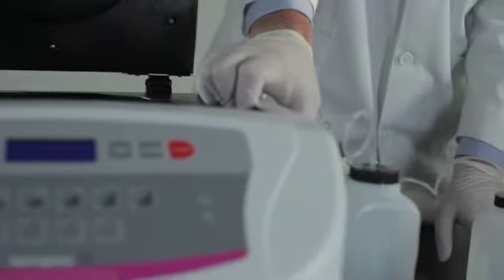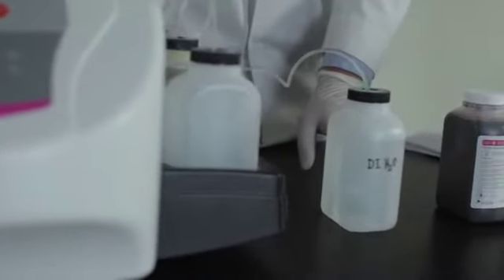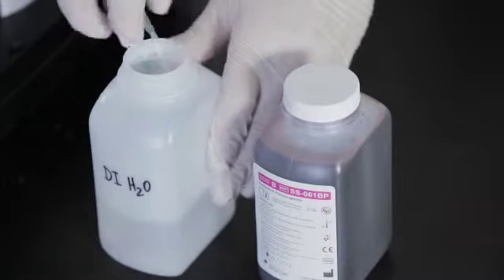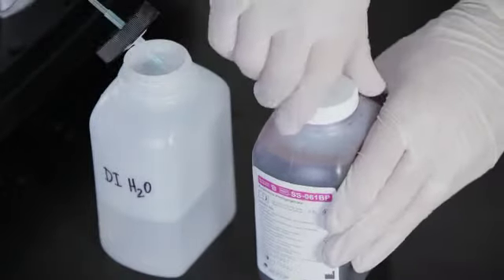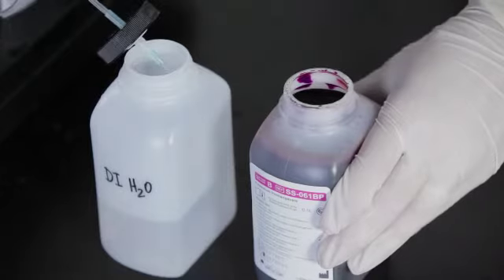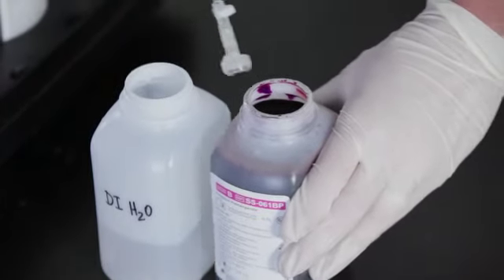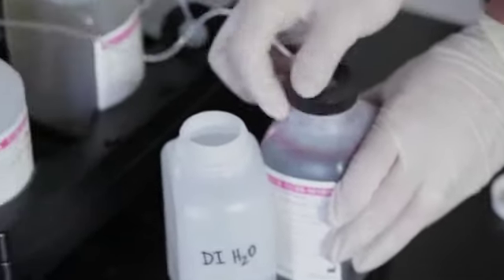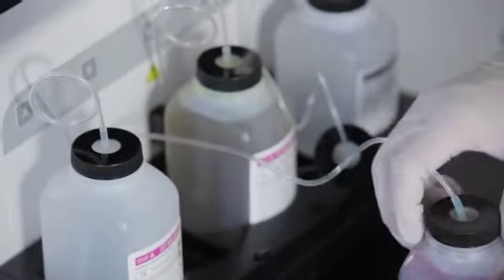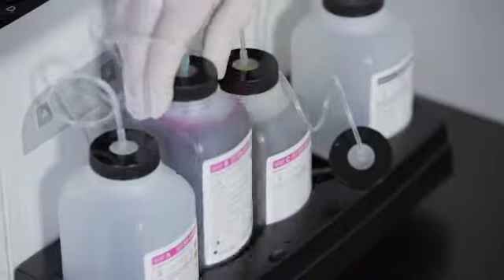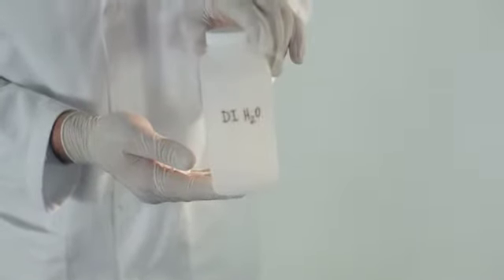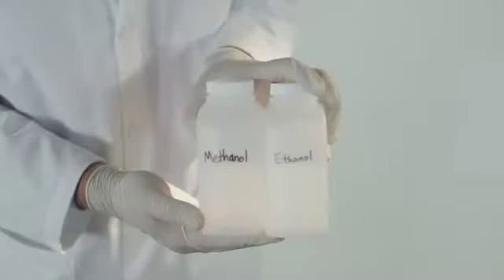When new, the stainers are shipped with methanol in the pumps and plumbing lines. Potassium permanganate and methanol cause a precipitate that can damage the pumps. Use water to pump out the methanol before the potassium permanganate is added. When either carbofuchsin stains or fluorescent stains are used, deionized or distilled water is used on the D line. Alcohol, either methanol or ethanol, is used on the E line.